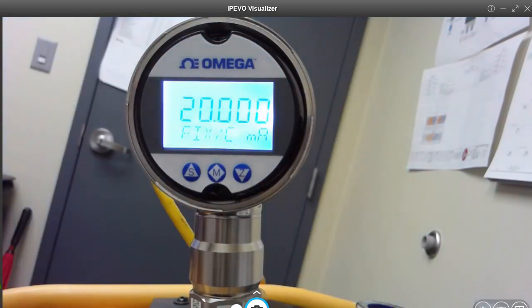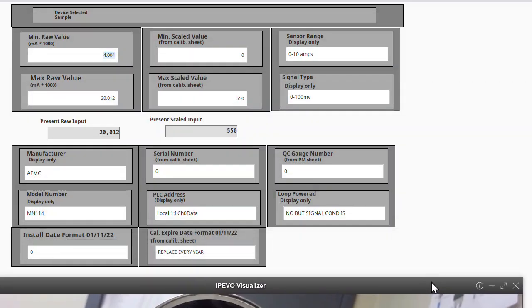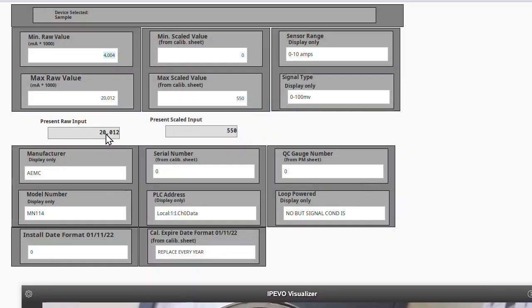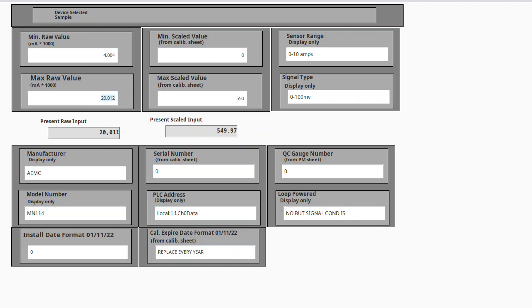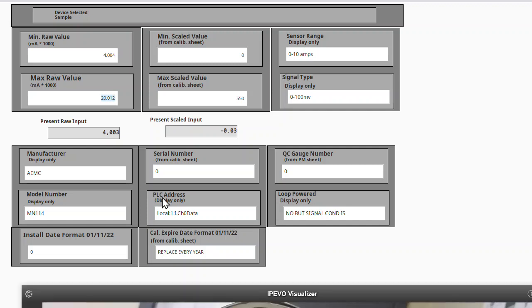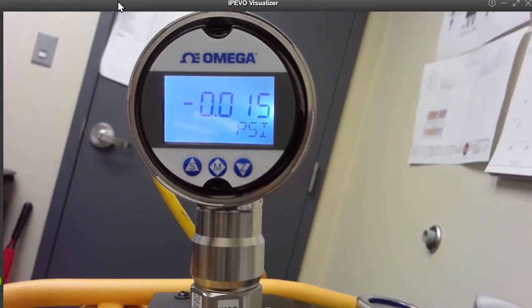And while we have it set to 20 milliamps, we're going to inspect our present raw input, which we'll see is slightly off. Our present raw is 20,000, or 20.012 milliamps. That needs to be placed into our max raw value. That will become our high signal. So take your present raw value and put it here. Now we're off that screen, so it went down. So let's go back. That generates our high signal.